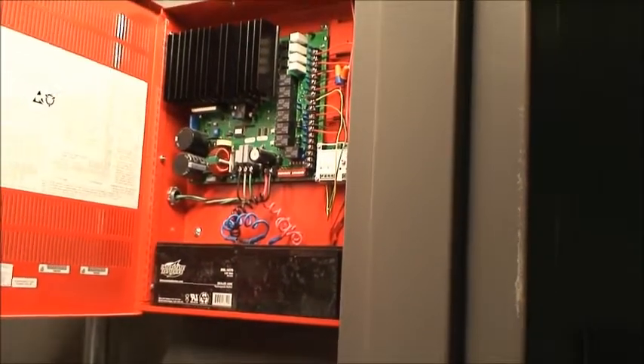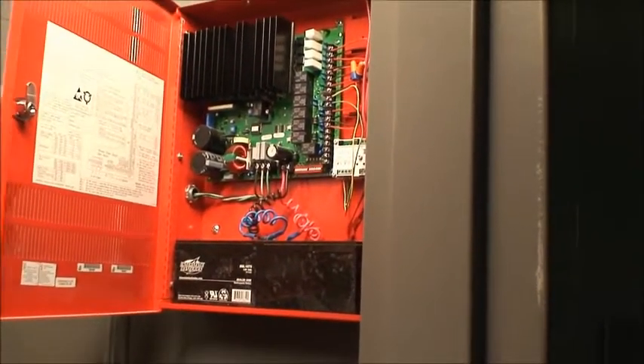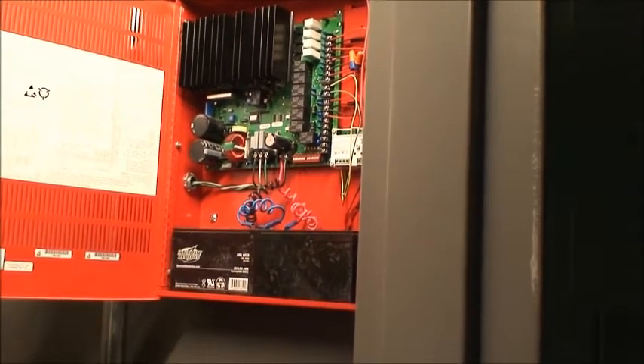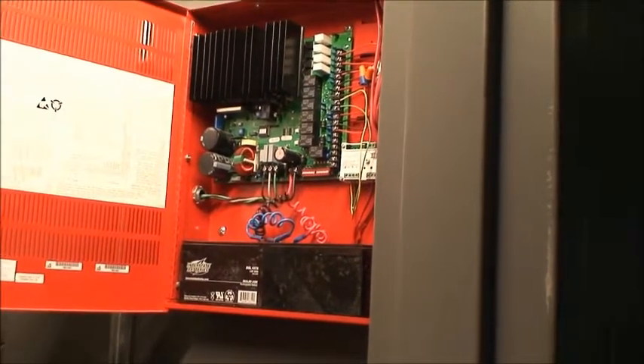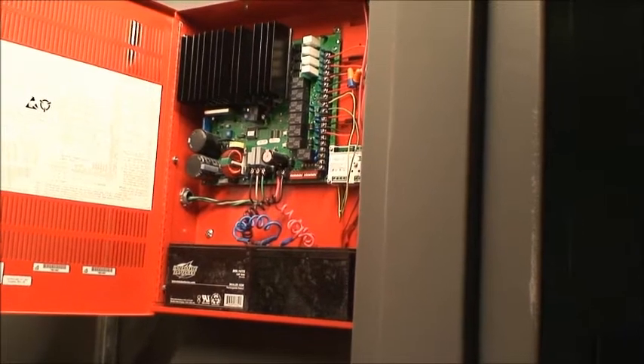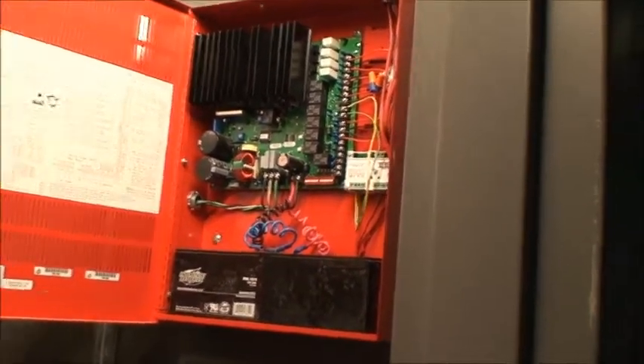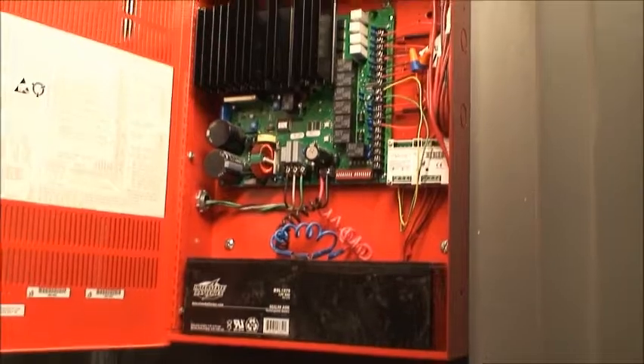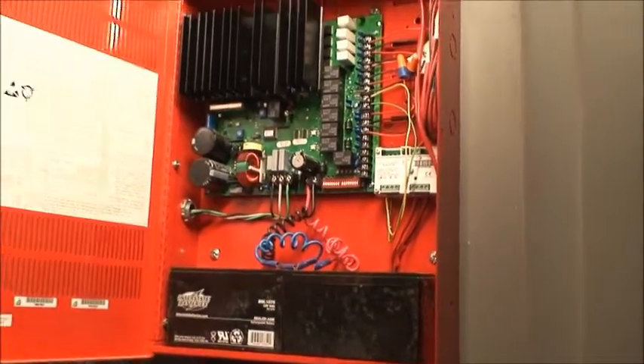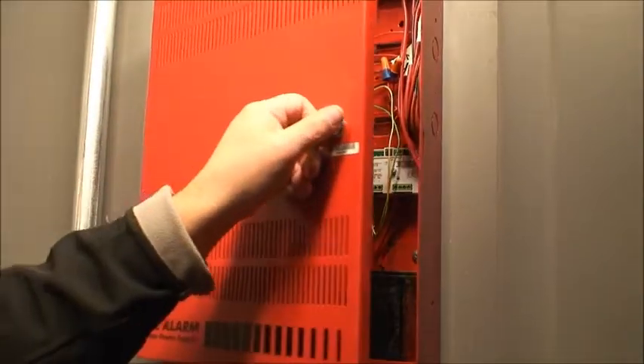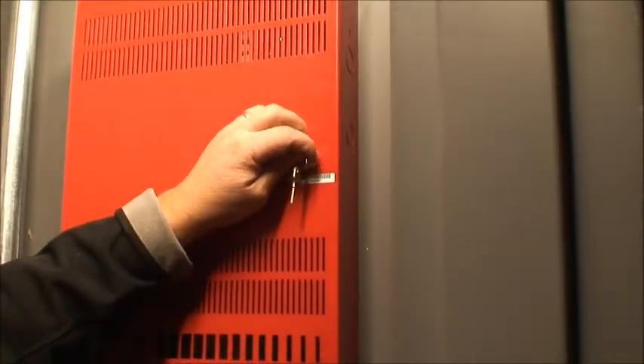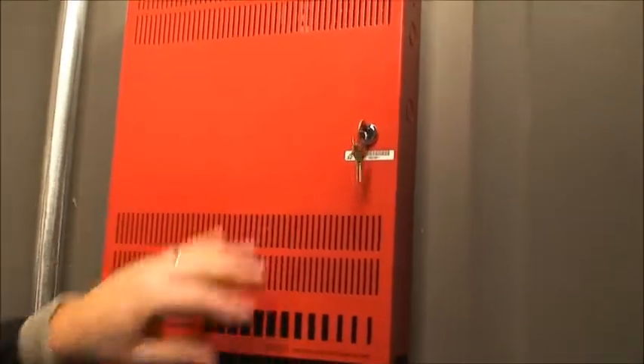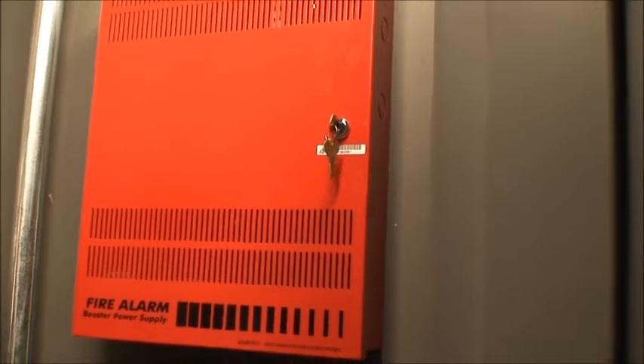Okay. So that clicking is always going to be there. It's a function of checking that everything's okay. It goes to all the cables because it has to monitor them. And if there's an open, if somebody takes one down, it's going to report. It's going to give us a trouble. You'll get trouble lights, and the trouble light will report to the panel, indicating what floor the booster you have trouble on is. It'll tell you where to go when you come up and find it.